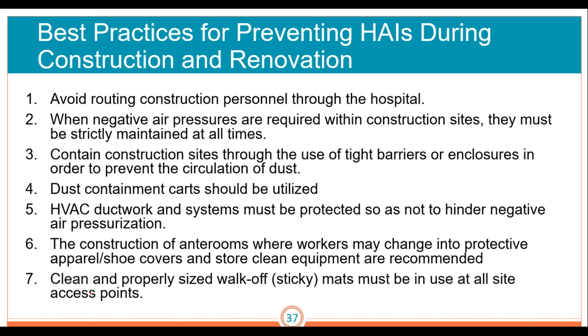Best practices for preventing HAIs during construction and renovation: avoid routing construction personnel through the hospital. When negative air pressures are required within construction sites, they must be strictly maintained at all times. Contain construction sites through the use of tight barriers or enclosures to prevent the circulation of dust. Dust containment carts should be used. HVAC ductwork and systems must be protected so as not to hinder negative air pressurization. The construction of ante-rooms for workers may change into protective apparel, shoe covers, and store clean equipment is recommended. Clean and properly sized walk-off sticky mats must be in use at all site access points.